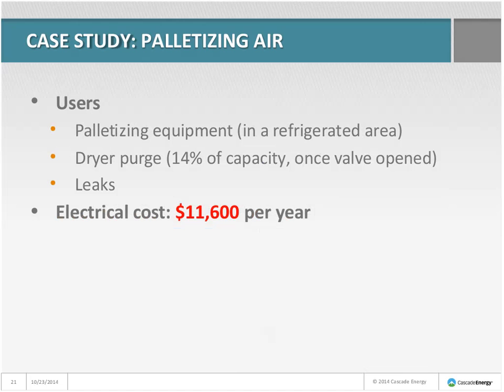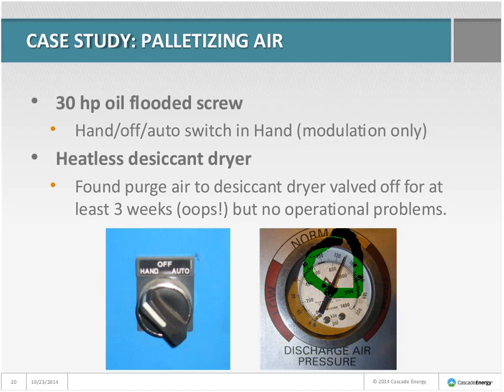Their users were primarily palletizing equipment on a refrigerated dock. What does oil-flooded screw mean? There are two basic types of screw compressors: oil-flooded and oil-free. On oil-flooded compressors, oil is injected into the rotors to seal the gaps and absorb most of the heat of compression. After compression, air goes through a sump or oil separator where a coalescing element scrubs out the oil, then to an aftercooler, filters, dryer, and on to users.